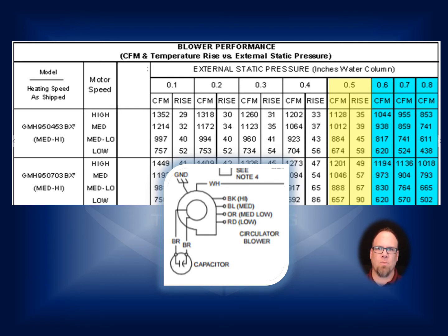Now think about this. Okay, I'm going to switch gears and I'm going to tell you something, and it's going to correlate to heating, and I think you'll get it. This is how critical it is that we set these up. In the past, some of the older furnaces that we put in had an air temperature rise of nearly 100 degrees. Okay, now you take the same BTU value in today's furnaces, our air temperature rise, according to many of the efficiency tests and setup charts, they want you to be somewhere around the 50-degree temperature rise setting. Okay, now the manufacturer has on their tag 35 to 65 or 30 to 60. Okay, but that's an operating range that's safe to operate that piece of equipment. It doesn't tell you anything about efficiency or anything like that. You still got to set it up.